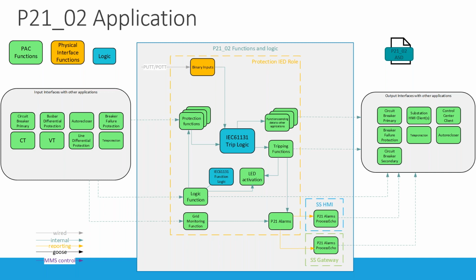We have a logic block with a specific 61131 logic attached, LEDs that get activated, the tripping itself, and data flow with other functions. Again, like the circuit breaker, there are interfaces on the left and right. The distance protection needs currents and voltages, input from the teleprotection application, and interacts with the auto-recloser. So this application too is a container on its own, but it also interacts with other applications.